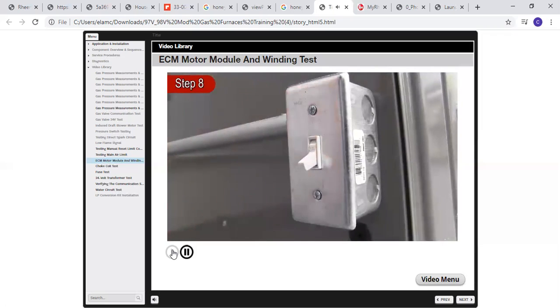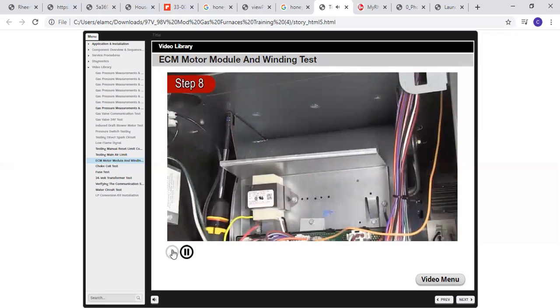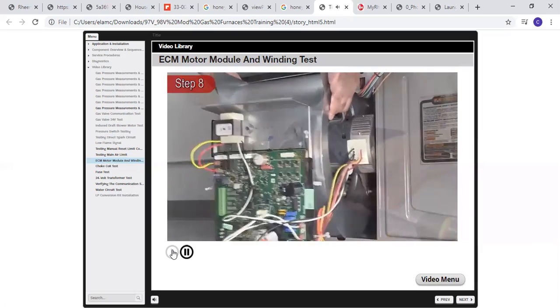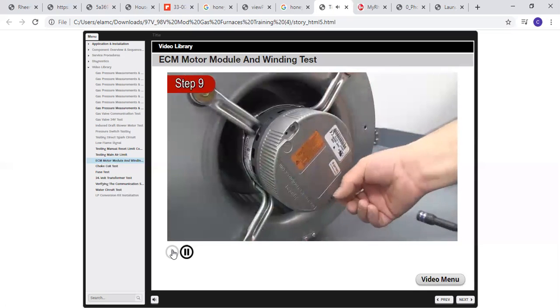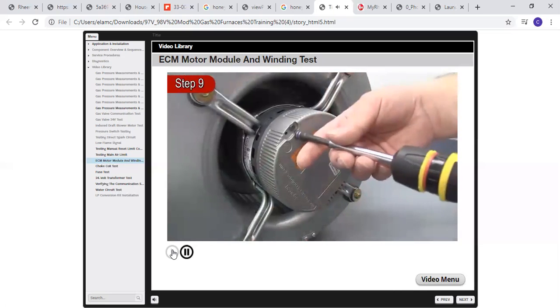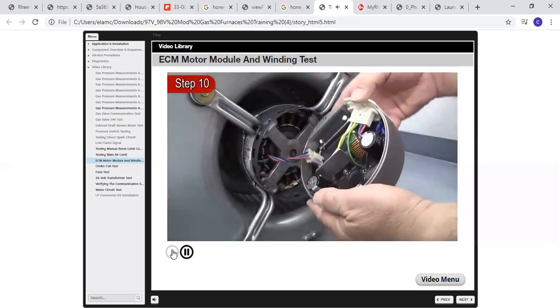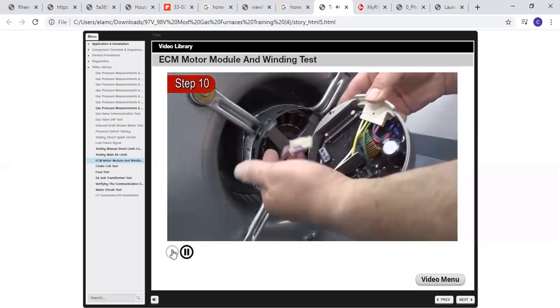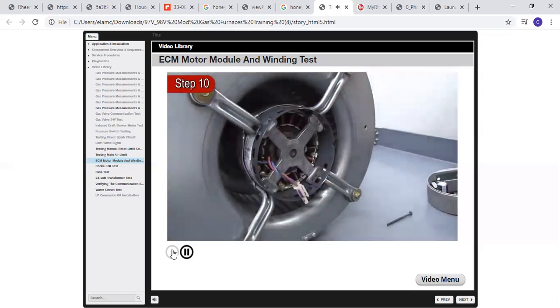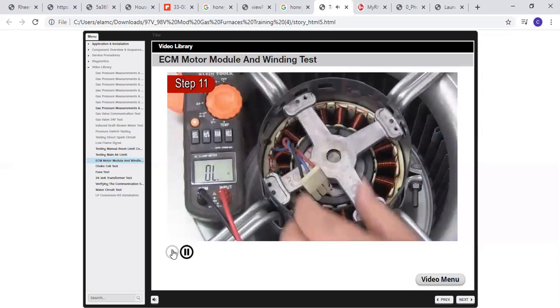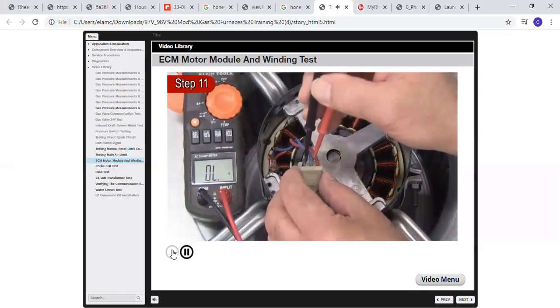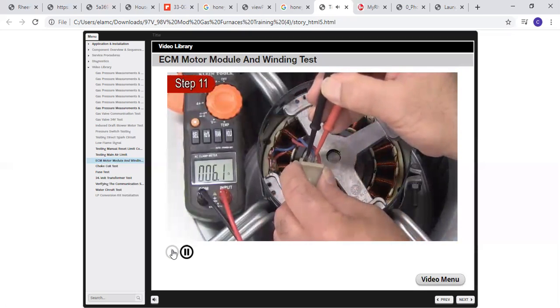Step 8. Remove power to the furnace and remove the screws that secure the blower motor to the furnace cabinet. Slide out the blower assembly. Step 9. Remove the 2 screws that hold the blower motor module to the blower motor. Step 10. Unplug the blower motor from the module. Set the module aside. Step 11. Using an ohm meter, ohm out the motor windings of pins 1 to 2, 2 to 3, and 1 to 3. Resistance should be within 10% across all combinations of motor windings.